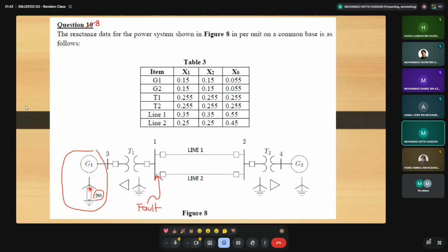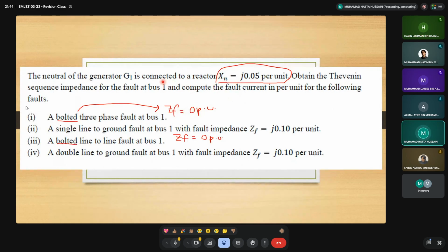Okay, at generator 1 here, we can see that we have the neutral reactance here. This is the difference between generator 1 and generator 2. So we have the neutral reactance here. This is basically the typical data given in table 3 here, typical data for all the components in the power system network. So we have the positive sequence, negative sequence, and also the zero sequence here. From here, we can see that we have the reactance Xn. Okay, this is the value.